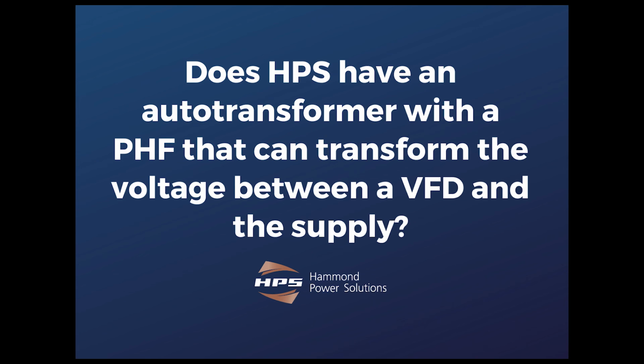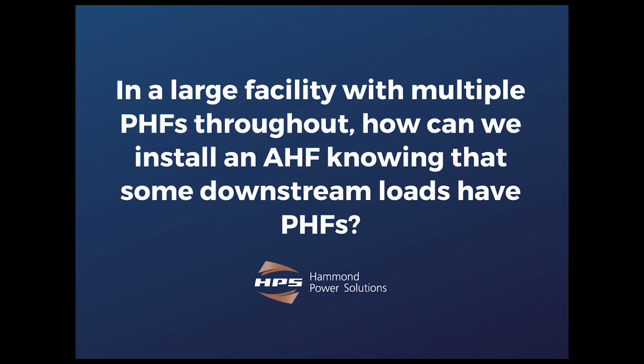Bob, let's assume this. Let's assume we have a large facility. We have multiple passive harmonic filters throughout that facility. How would we, or can we, go about installing an active harmonic filter with the knowledge that some of the loads downstream will have passive harmonic filters? It really shouldn't be a problem.